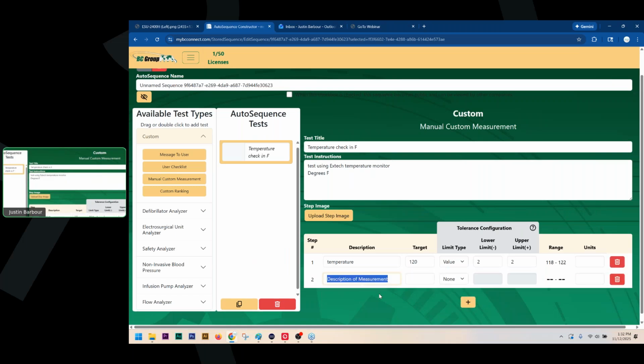So now let's say I'm doing an RPM check. Maybe this magical treadmill also has a temperature reading for some weird reason. Okay, we've got an RPM check, we're looking for 6 mph. We're going to do a specific level, and we need plus or minus 1. At 11, Jesus, that's fast. Okay, 1 - so as long as the speed of my treadmill is between 5 and 7 miles per hour, that's acceptable.